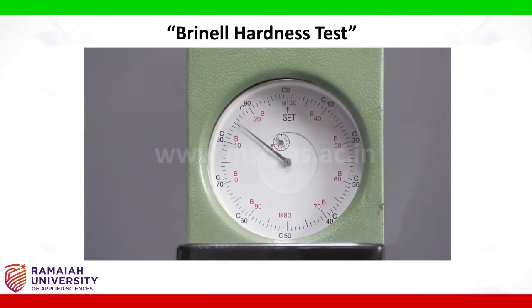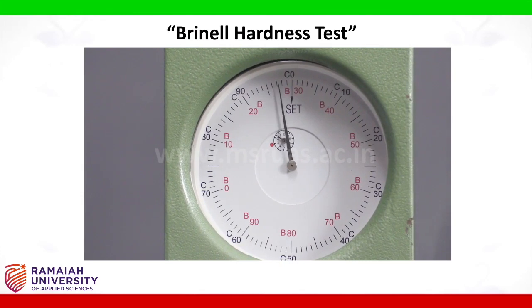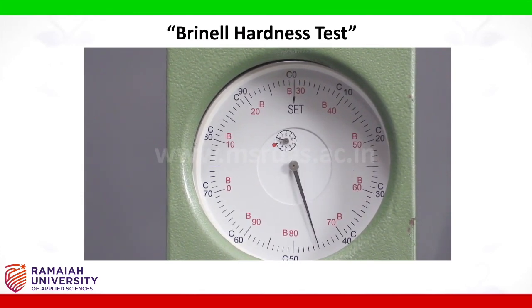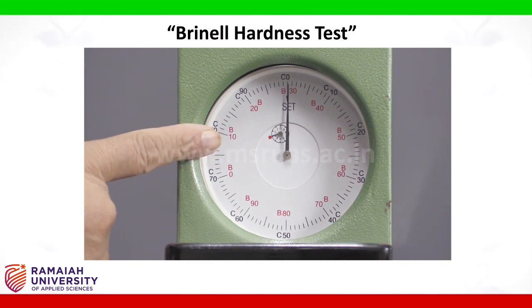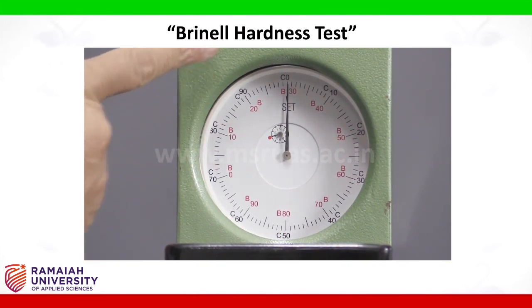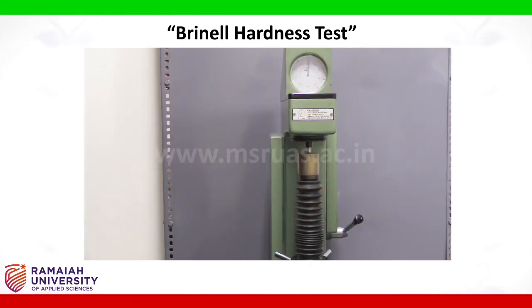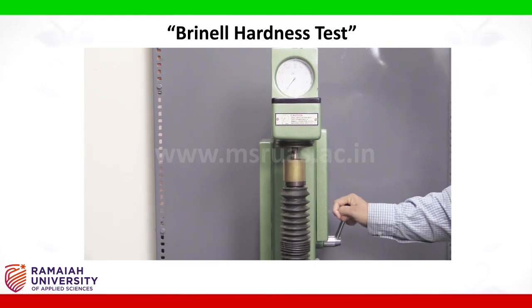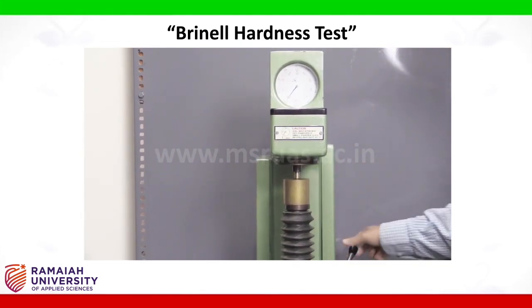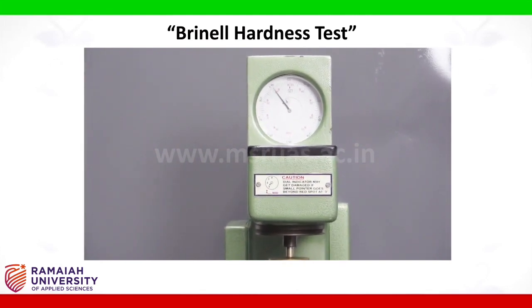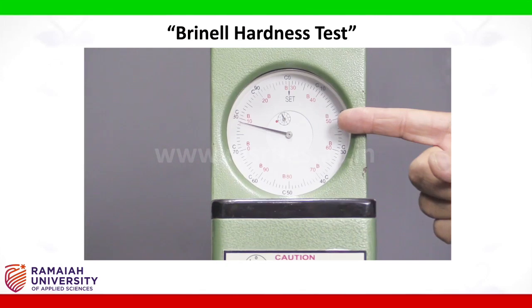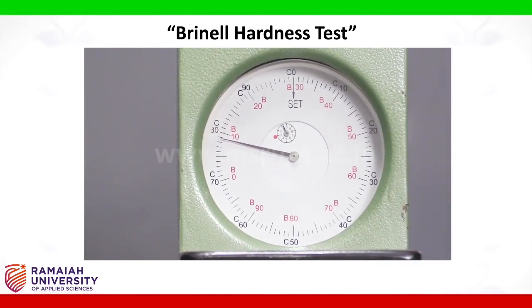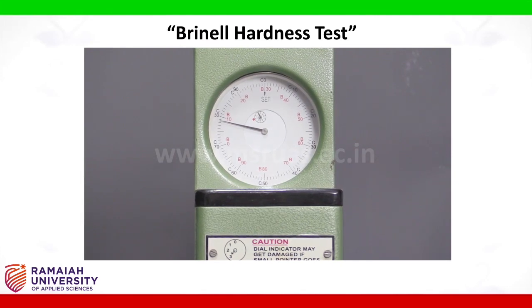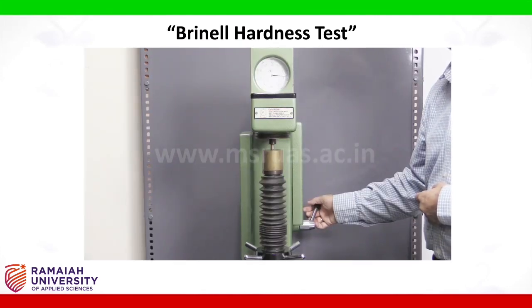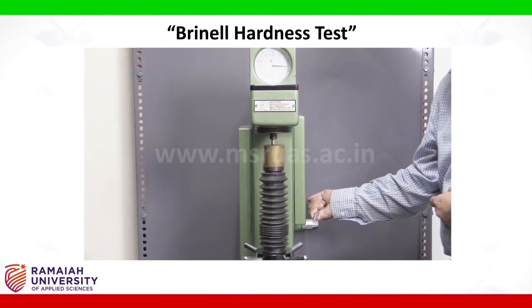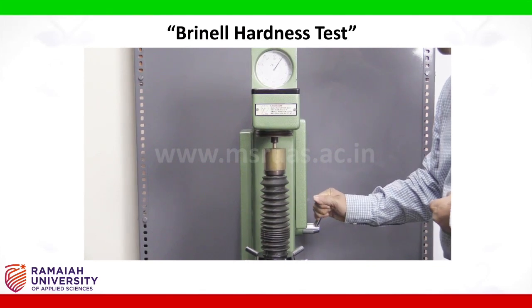The indicators on the dial gauge are moving. When the minor load is applied, the smaller dial, please note, the smaller indicator has coincided with 3 and the larger indicator has coincided with 0 in the red B scale. After applying the minor load, while I am applying the major load, the dial gauge moves. After the dial gauge indicates a particular reading, it stops at that reading. The dwell time is provided for ensuring elastic recovery. After 15 seconds of dwell time, I am now removing the major load.